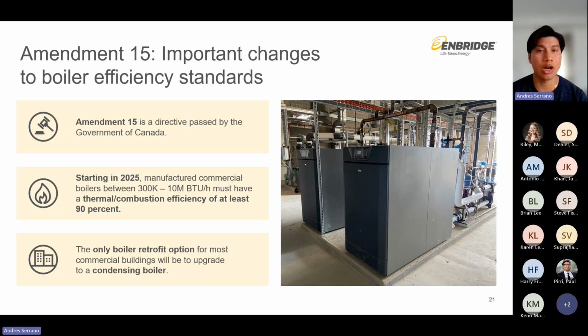So similar to our special offers for fixed incentives, we also have special offers for our custom incentives. But before I get into it, I would like to first discuss Amendment 15. Amendment 15 is a directive passed by the Government of Canada. Starting in 2025, manufactured commercial boilers between 300,000 and 10 million BTUs per hour must have a thermal/combustion efficiency of 90%. So that means that starting in 2025, the only boiler retrofit option for most commercial buildings will be a condensing boiler.